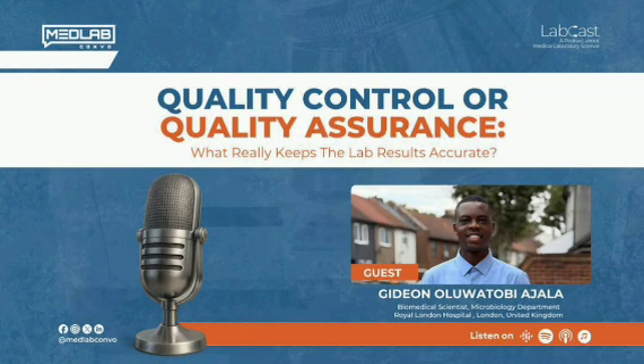I've worked in a laboratory before, while I was in Nigeria, in the hematology department. That day, we had done the QC in the morning on the machine. The machine was working perfectly. Then there was a break in the machine. We had to do some repair along the line. After the repair, we were supposed to do the QC again. Then we ran a sample on the machine. Fortunately, the sample that was being done belonged to a colleague.